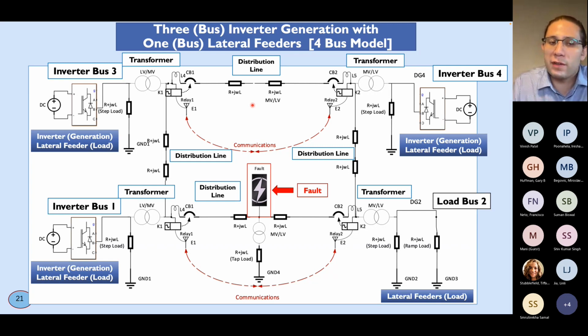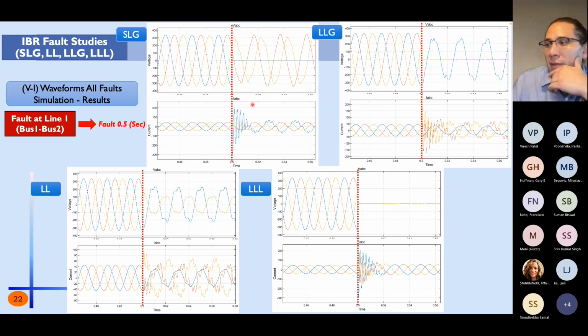And we could identify different cases, and we could validate and study the different types of loads as I presented before. In this example, I'm showing how four different faults behave with inverter operation. On the top figure, we have the single line to ground fault. And as we can see, we have a small transient during the fault, but this is due to the controllers and the limiters. They are trimmed in our control. And we can see that our current is no longer huge.